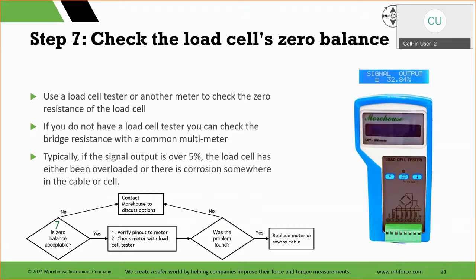If you have a bunch of techs that go out and use them in the field, someone comes back and says, hey, I didn't overload that. And you say, well, before it went out, the signal output was 0.2, and now after you went out, it's 32.84. That means your tech overloaded the load cell, or it could have happened in shipping or something else, but at that point someone did something and the load cell's really not fit for use.